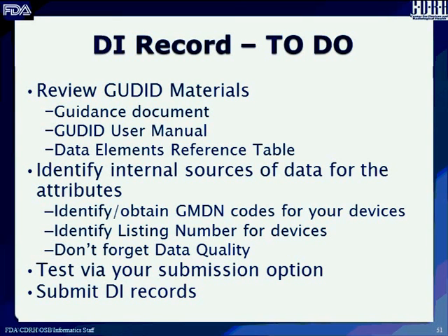The device information reviewed successfully. Here is the DI record publish date, and if I submit this, the record has been submitted, and you see it's giving me the grace period. Because this is a test system, we've set the grace period to be 1 day, so it's telling me I have until July 22nd to update any fields in this record that would otherwise create a new DI trigger.